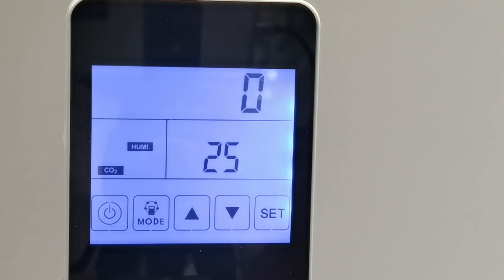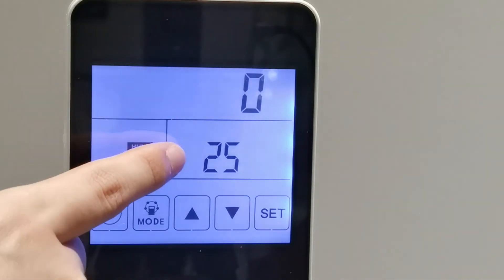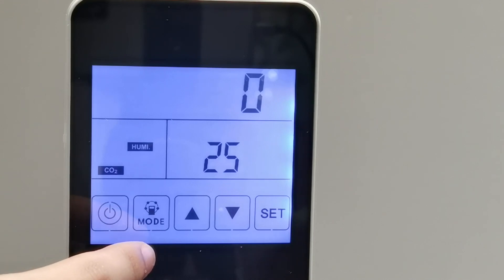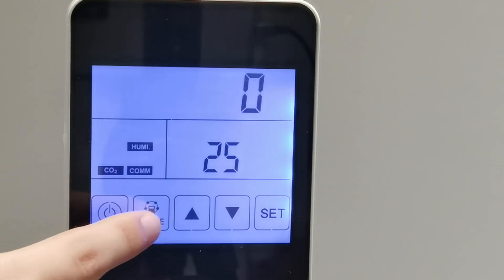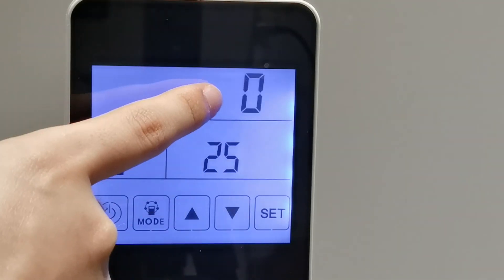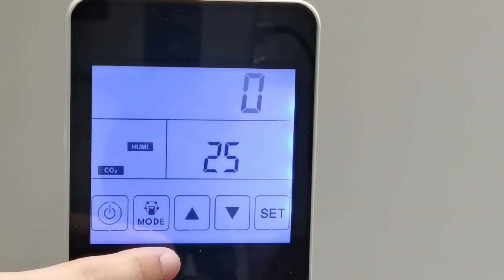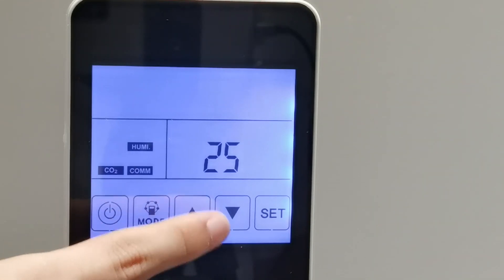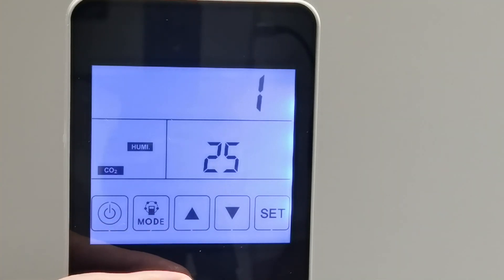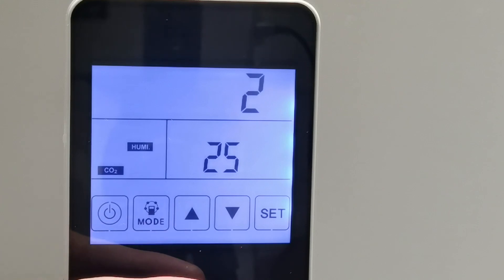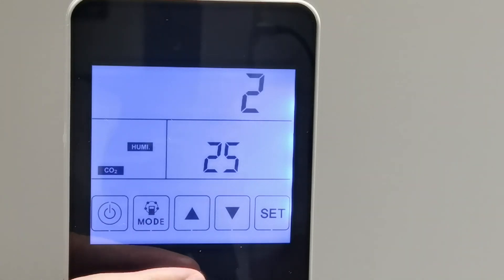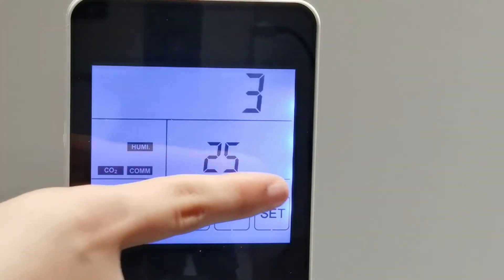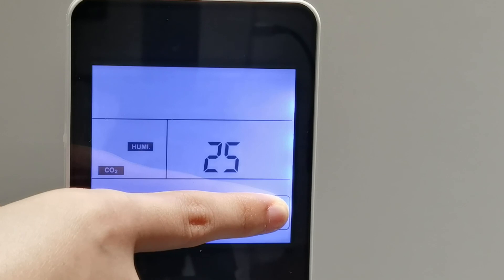Parameter 25 is the filter alarm setting. If we want to change the filter every 45 days, select value 0 — this is the default. Value 1 means 60 days, value 2 means 90 days, and value 3 means 180 days. The default value is 0, meaning 45 days.